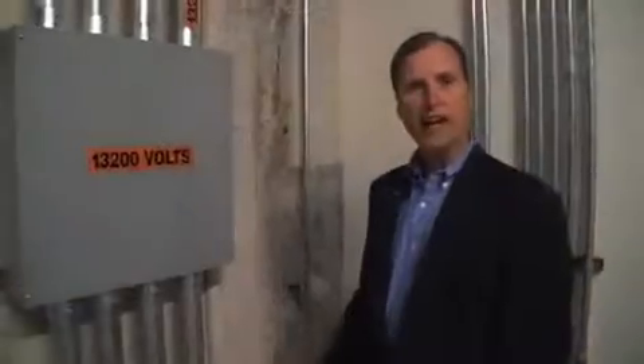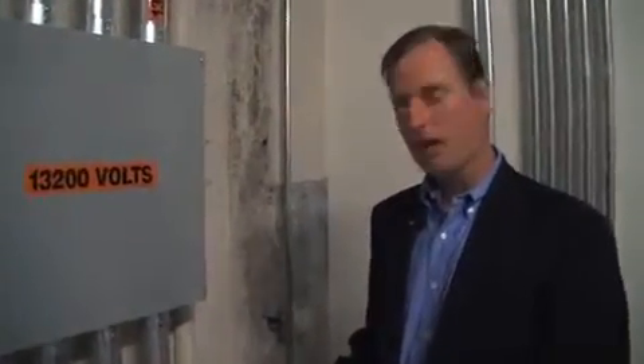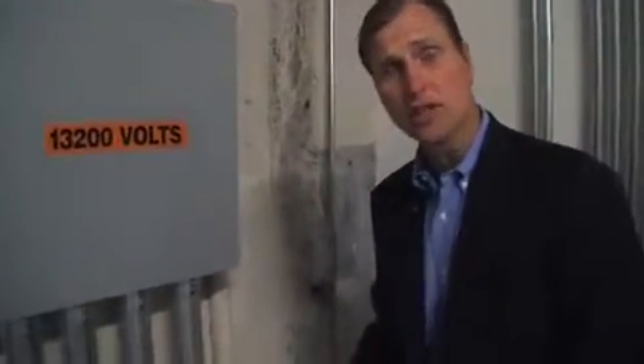We also have 5,000 square feet of storage space in the basement level. We bring in high voltage from the utility company, so it comes in at 13,200 volts into the facility, and this is our own private feed from 2 separate substations. You saw where the power comes in from the utility company. In the event of a utility failure, the purpose of the UPS and the associated battery string is to carry the load until the generators get up to speed, and that normally takes about 7 seconds.